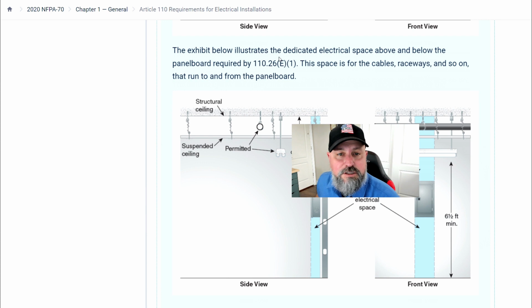The exhibit below illustrates the dedicated electrical space above and below the panel board required by 110.26 E1. This space is for the cables, raceways, and so on that run to and from the panel board. So another side view, dedicated space. So it's right there, under, above it. And you can see this is not in there. The pipe is out here, it's permitted. But nothing is allowed to come through that area right there from this depth all the way up to 6.5 feet or to the structural ceiling.